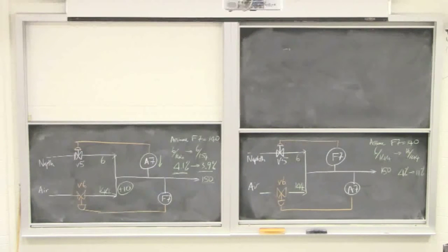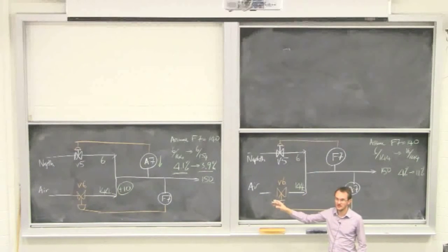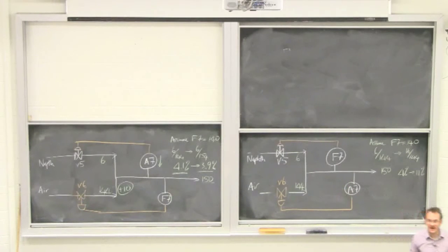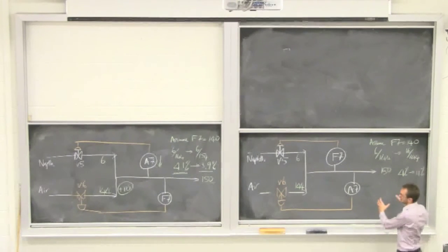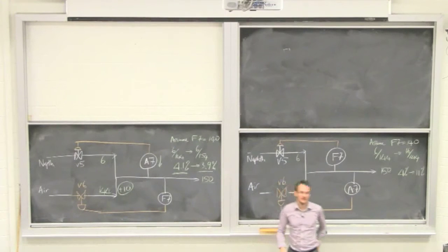The problem with that is that you may get disturbance downstream. All those disturbances will, of course, also propagate further downstream and cause problems for the subsequent control loops. The main reason why you don't want to do this one is because the interaction between the loops over here in this pairing is far greater than the interaction over there. So the ideal case is, of course, that you have control loops that never interact. A change in one variable never affects the others. But we see in many processes we get interaction. You get stronger interaction, as shown over here, and then very weak interaction, as shown over there.